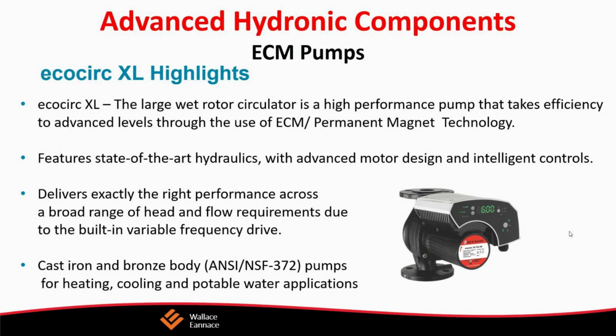As you can see, if you set it for proportional pressure, as the pressure increases, the speed will start to decrease, and there are also a constant pressure curve and a fixed speed curve. But if you have larger applications.